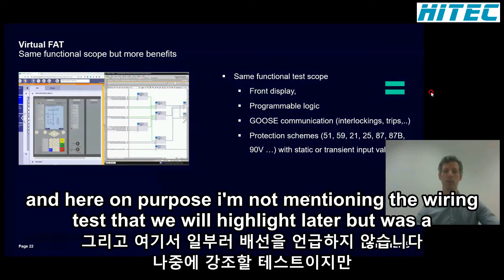Here, on purpose, I'm not mentioning the wiring test that we'll highlight later, but more the functional test: how to validate the front display configuration, critical for local operation of the device later; how to validate the programmable logic with all the interlocking equations or special applications manually configured; to validate communication between virtual devices using the IEC 61850 GOOSE protocol or the protection interface for differential protection; and also the possibility to test any protection function, whether overcurrent protection, distance protection, or even busbar protection.